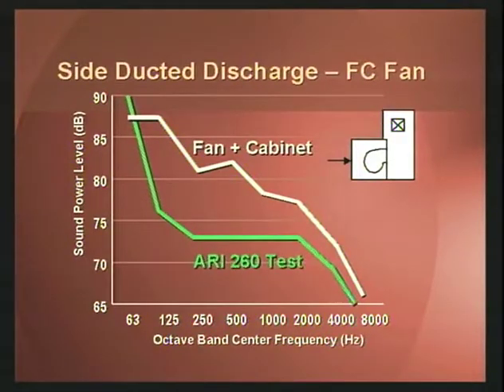That typical approach is where they will take a fan, sometimes fan tested data, and add to that a cabinet effect. That cabinet effect is usually predicted by using classical acoustical equations. They may be non-flow in nature. Even in this case, as we show on the slide, what we have here is a plot of sound power data in octave bands. And the green curve that you see here is the ARI 260 test data. What we have test data for is the figure to the top right, the cartoon of a horizontal supply fan going into two stacked plenums and with a ducted discharge that is actually 90 degrees from the flow path. The green curve, as I mentioned, is the 260 data for that configuration.